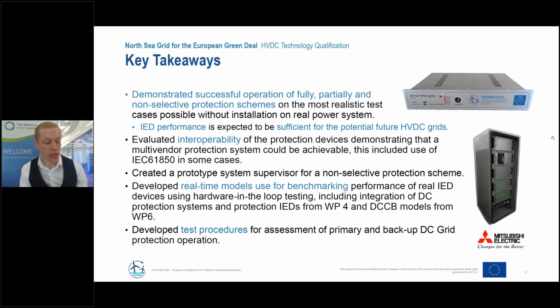An interesting question that came in aimed at the protection demonstrators was whether there was an impact on the primary plant ratings from the inclusion of a DC breaker. Without extensive investigation, considering the use of replica control and protection panels, and that we were able to integrate the physical IEDs and breaker models without changing settings on the protection scheme as set up for an existing system that didn't have DC protection, and it worked, it suggests there wouldn't be a significant impact on the primary plant, as none of the primary plant protection triggered during this testing.